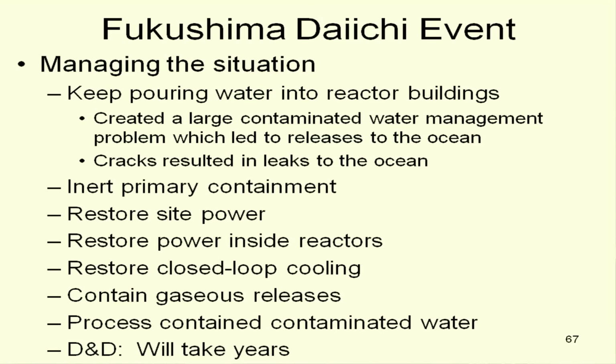The sumps and the basements just kept filling up. They didn't want to release it because of the radioactivity, but they had no other place to put it. So eventually they took some of the lowest concentrations and did release that to the ocean. And with time, they got some portable tankage, and now they're putting in water processing where you run it through ion exchange and get mainly the cesium, which is the problem, out.